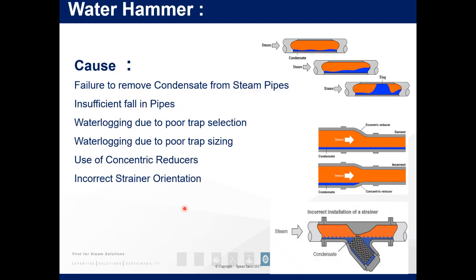So the causes here: failure to remove condensate from your steam pipes, insufficient fall in pipes. We try to maintain over steam lines a 1 in 100 fall, so for every 100 meters, it will drop by 1 meter. Waterlogging due to poor trap selection, so effectively your condensate is building up. Waterlogging due to poor trap sizing, so the trap is too small to clear the load that you have. Use of concentric reducers, so effectively ones where you create a step. Incorrect strainer orientation.